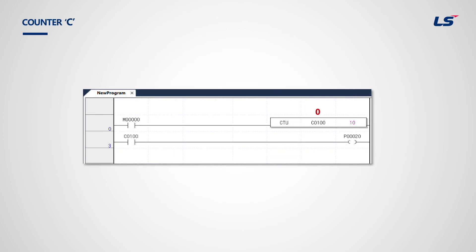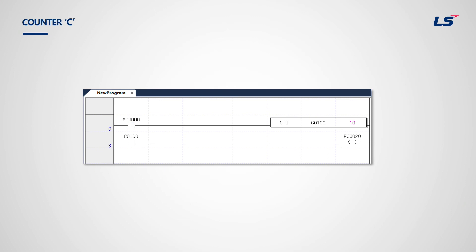C is for counter. The CTU function is an up counter. In this example, the set value is 10. It will count M0's count pulse when M0 has a rising edge. C100 will increment, and when it has increased 10 times, C100 will turn on and P20 output will be on.